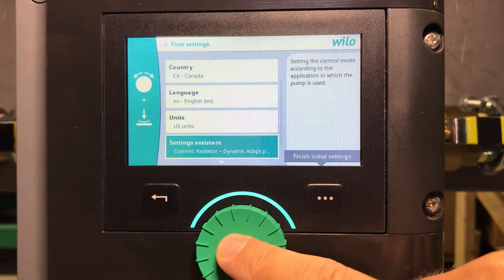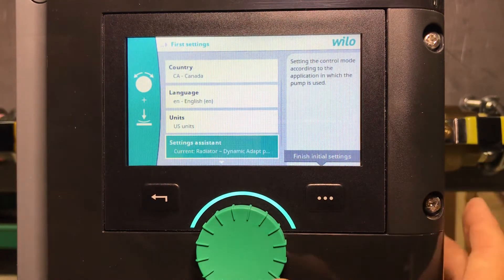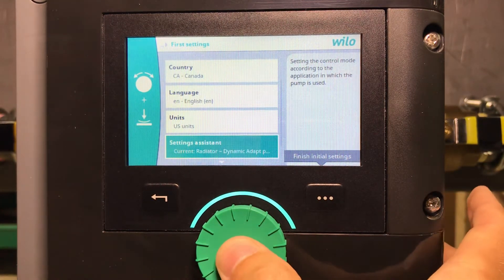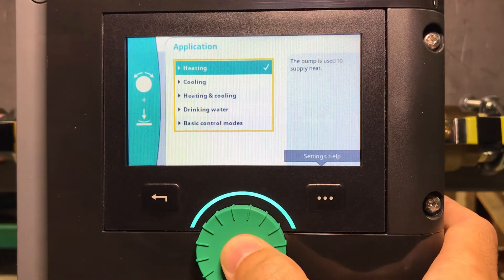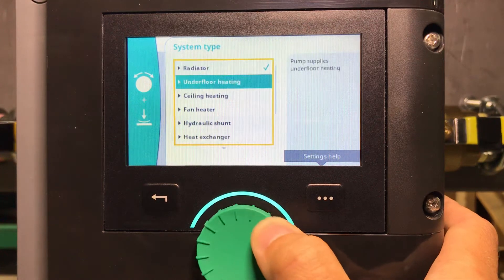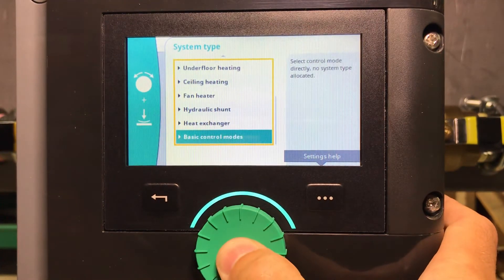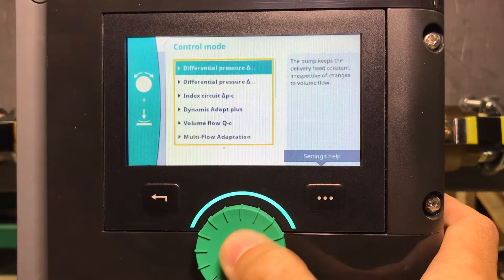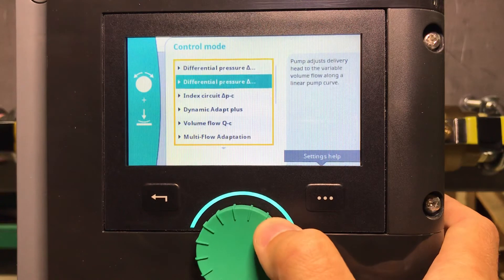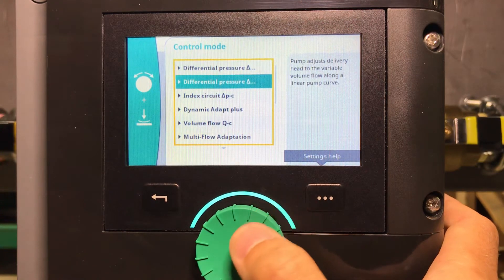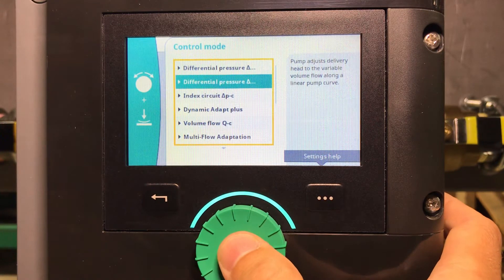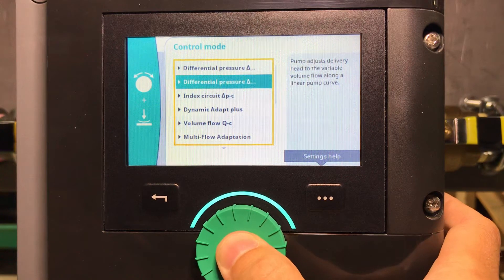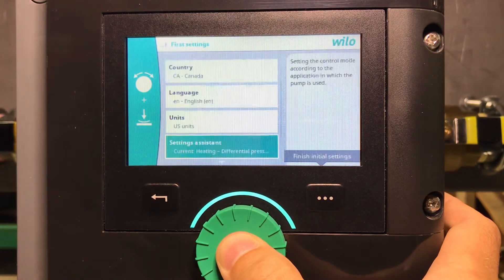In the settings assistant, this is where you set your control method. For the purpose of this video, this pump is installed in a heating application, and I will go with basic control modes. I'll choose proportional pressure because this is the most used control method for heating applications.